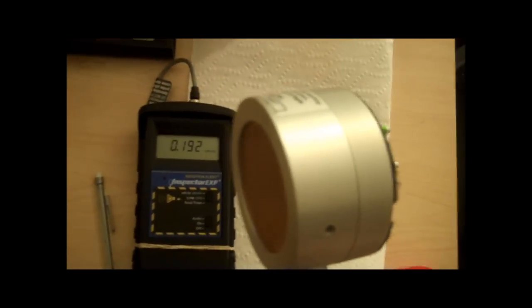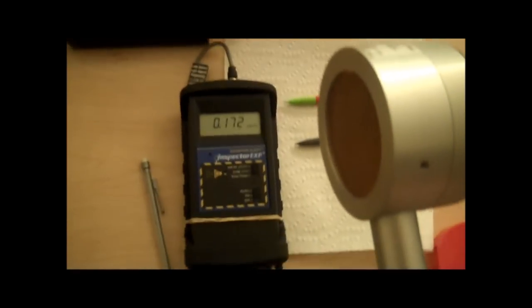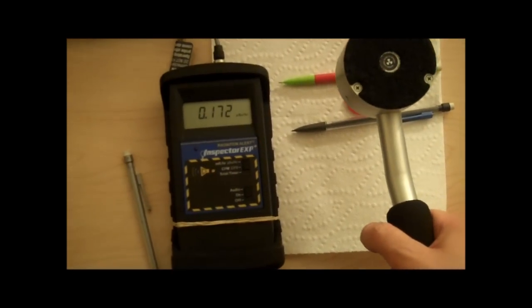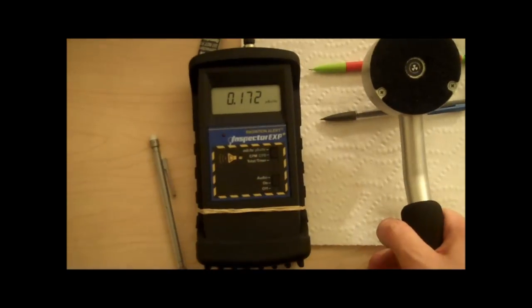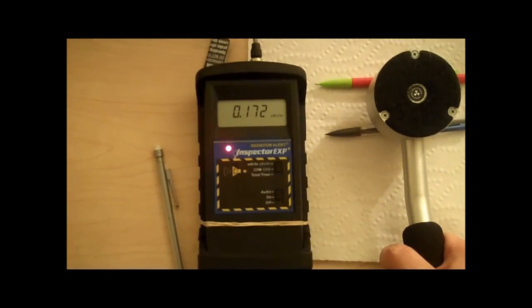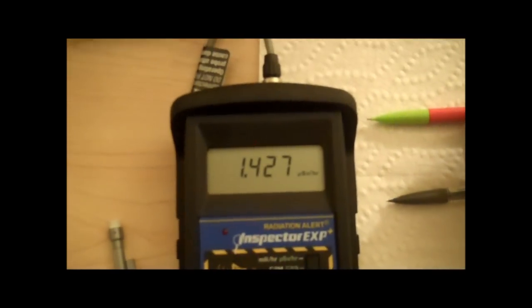You must already know your background and how to remove it and how much it is. All of that gets messed up. So this is not something you want to run around with. You want to be normally at factory calibration, which is setting 100. I'll show you how to get back. As you approach the polonium, the microsieverts go up, and this is probably accurate.